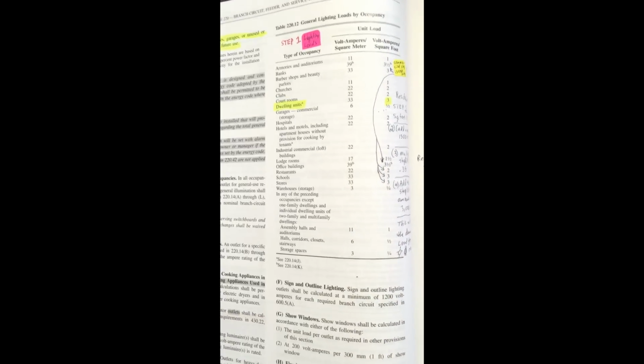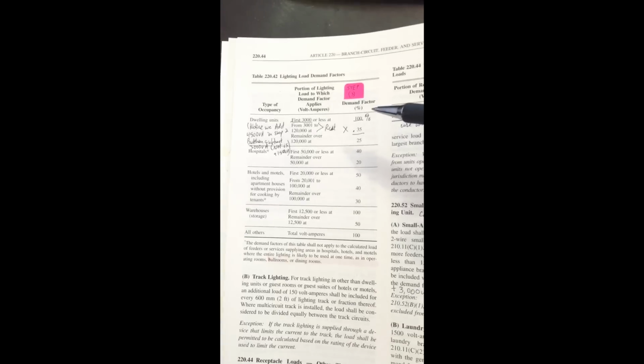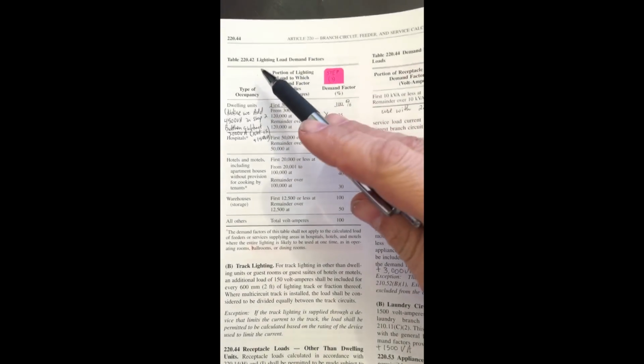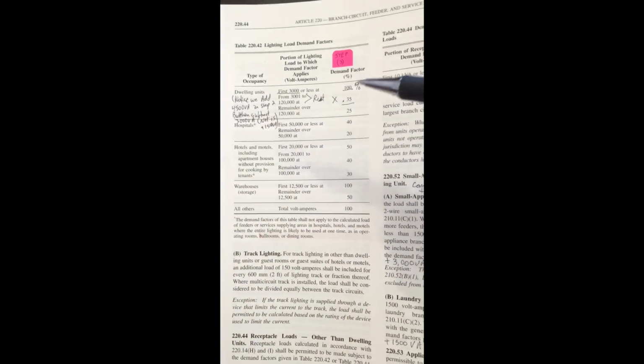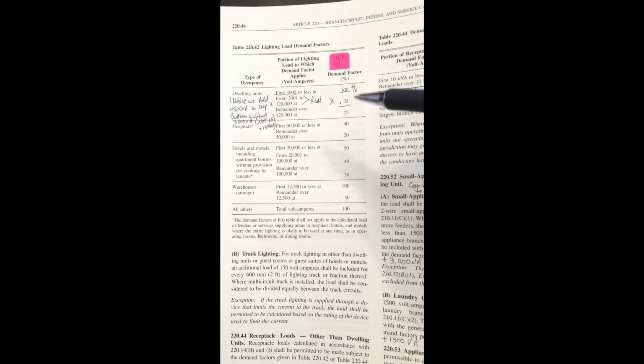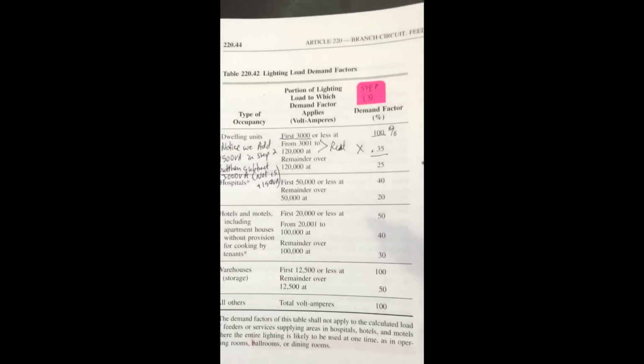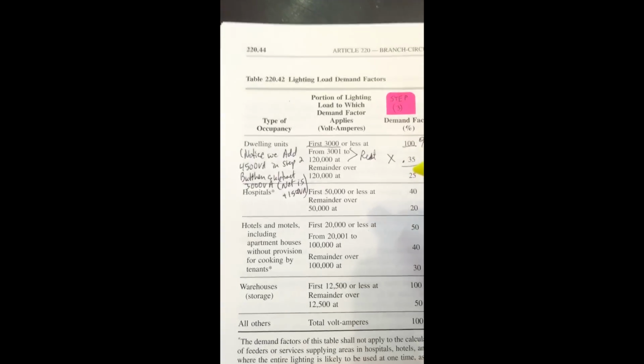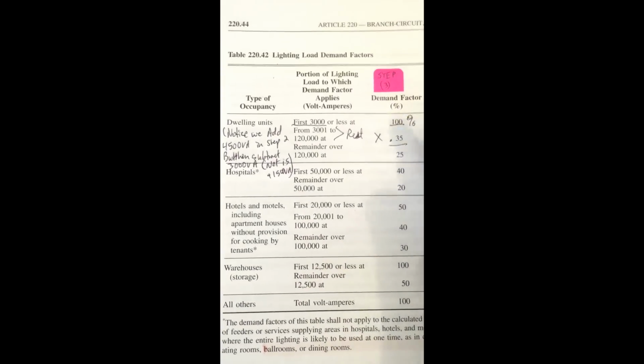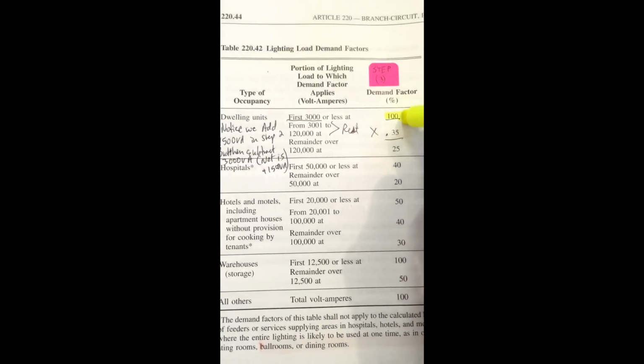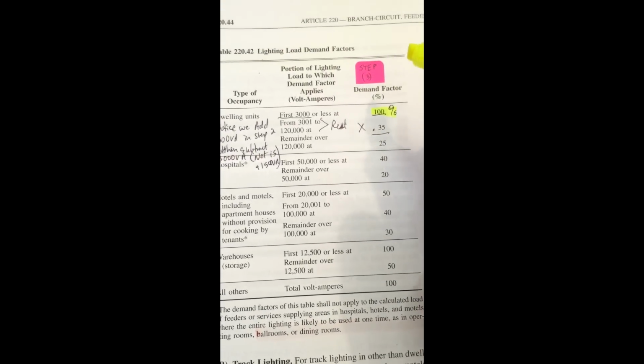We get to the reality of it by the next page over with a table at the top left-hand side of page 70. This table, 220.42, is the reality sinking in, and this is going to give us a derated calculation that's a little bit closer to what we actually expect might occur in the real world. The first 3,000 volt amps of our calculated value will be kept at 100% of that number. In other words, I'm going to keep 3,000 volt amps right off the bat. I'm not going to derate that at all. I'm going to highlight that just so I don't lose it.